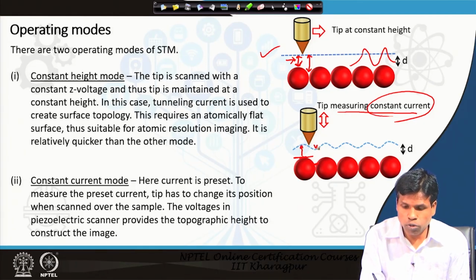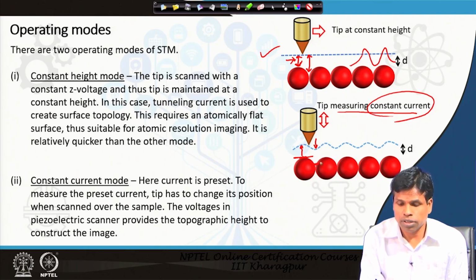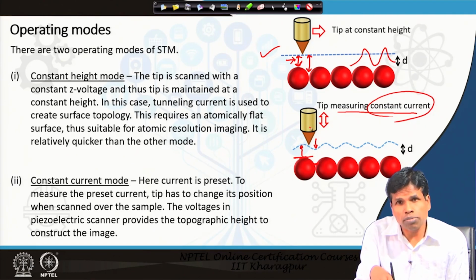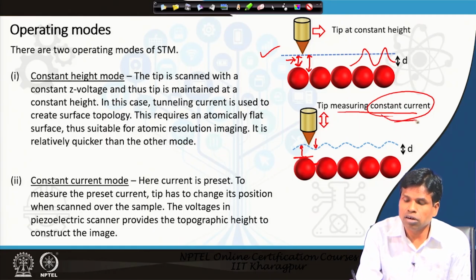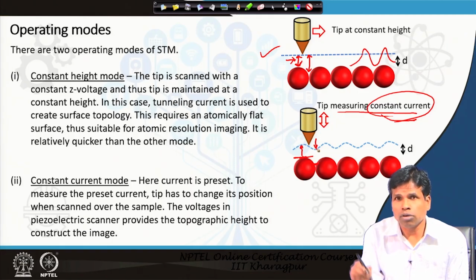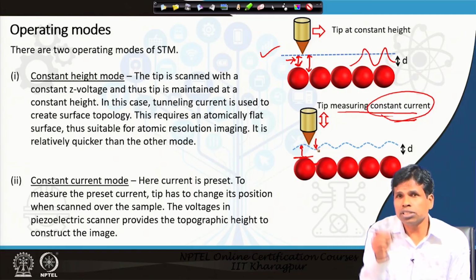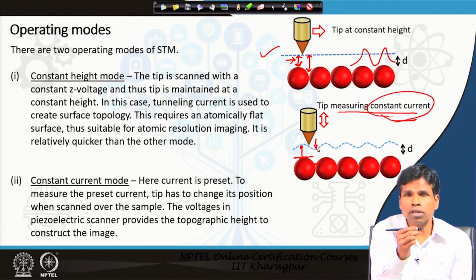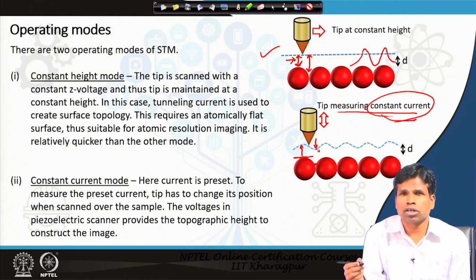But again, as you see, the tip has to come downward here, because the sample is seen at a little lower depth. So, in order to measure constant current, the tip has to come down, by suitably applying a voltage to the piezo element. Our feedback control will pass the information on how much current it is seeing, and therefore how much the tip has to come down to see a preset or constant current. In this way, the tip has to go up and down to see constant current, and how much the tip is going down and how much it is going up will be utilized for constructing the image.